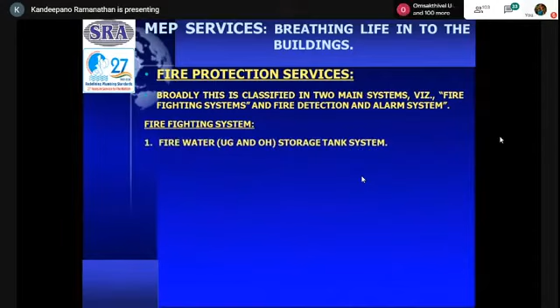Firefighting system number one comprises fire water, underground and overhead storage tanks, and fire water pumping systems, which involve main pumps as well as mandatory backup. In case the main electrical-driven pumps fail, you are supposed to have diesel engine-driven pumps also. So the fire water pumping system comprises electrical pumps, diesel pumps, and pressure-maintaining jockey pumps — a small pump to maintain pressure in case of small leakages in the piping system.